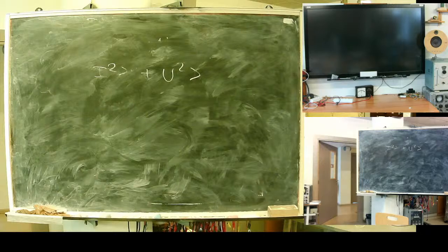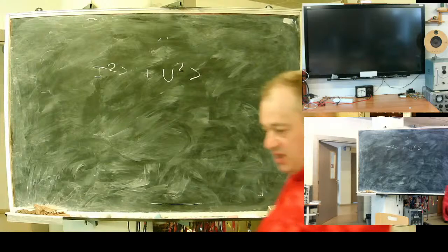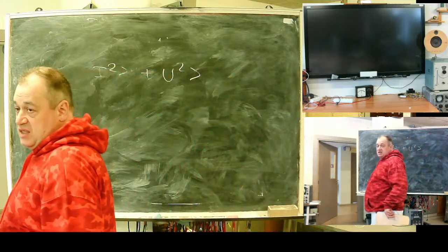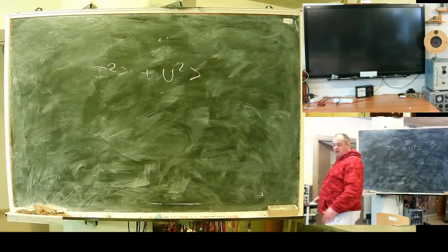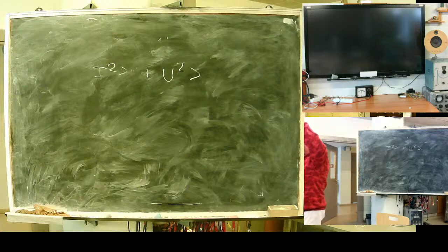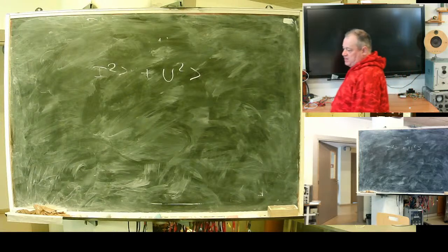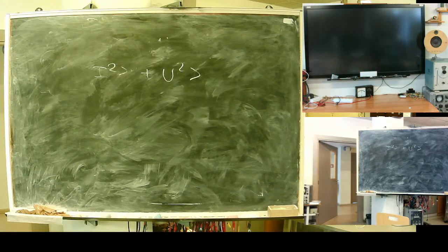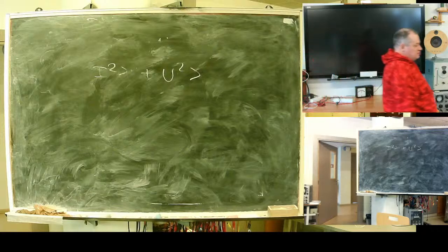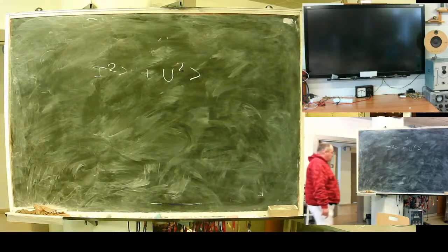In a short time, earthing, rods, everything corroded. And when lightning struck, the whole tower rose in potential above ground level, and all three insulators were overshot instantly. So, an instant three-phase fault. It's seen in reality. So this old technique with negative sequence is not reliable.